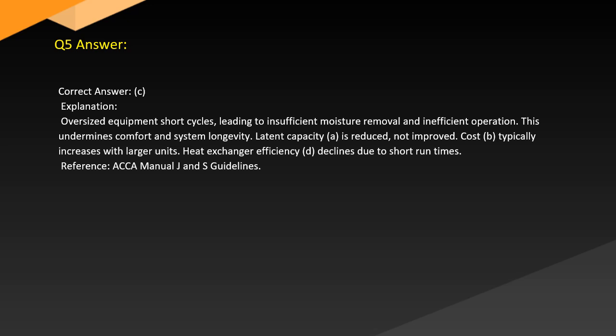Answer. Correct answer: C. Explanation. Oversized equipment short cycles, leading to insufficient moisture removal and inefficient operation. This undermines comfort and system longevity. Latent capacity, A, is reduced, not improved. Cost, B, typically increases with larger units. Heat exchanger efficiency, D, declines due to short run times. Reference: the ACCA Manual J and S guidelines.